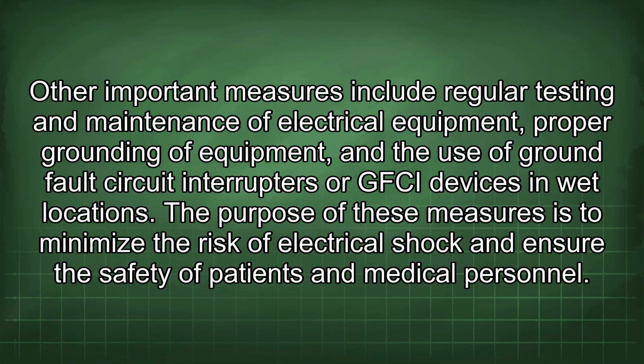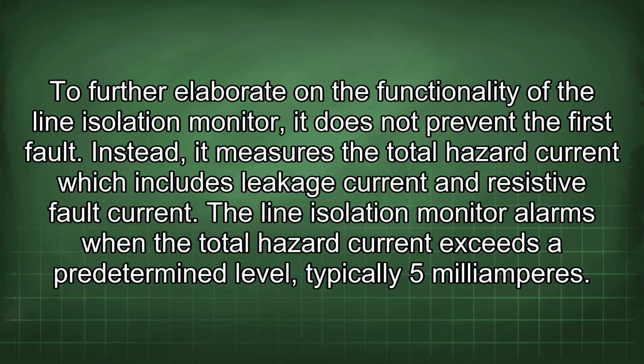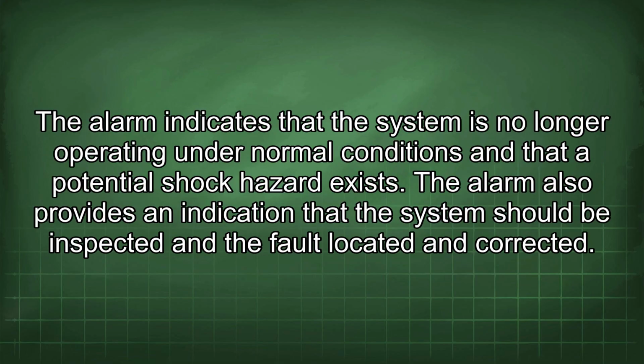To further elaborate on the functionality of the line isolation monitor, it does not prevent a first fault. Instead, it measures the total hazard current, which includes leakage current and resistive fault current. The line isolation monitor alarms when the total hazard current exceeds a predetermined level, typically 5 milliamperes. The alarm indicates that the system is no longer operating under normal conditions and that a potential shock hazard exists. The alarm also provides an indication that the system should be inspected and the fault located and corrected.